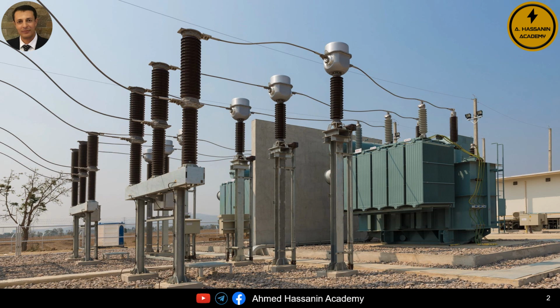Of course, we all know that this tripping is often due to the occurrence of magnetizing inrush current inside the transformer. Typically, we may wait for a minute or two and then attempt to energize the transformer again. As a result, the transformer may accept the energization, or unfortunately, it may trip again and fail to remain connected, and this process may repeat. So why does the transformer sometimes accept energization on the first attempt? And why might the same transformer only accept energization on the second, third, or even fourth attempt?